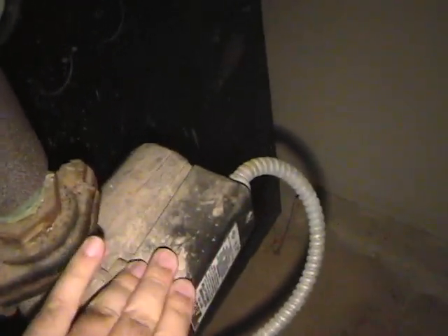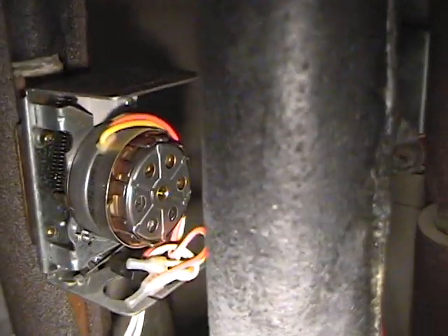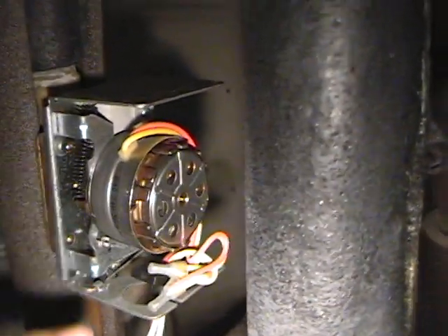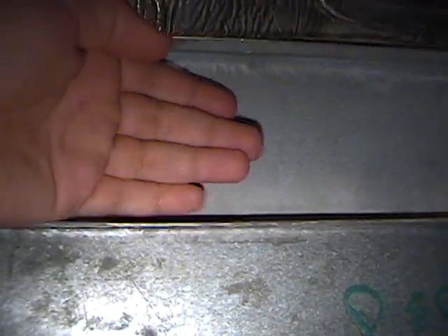Okay, so right now, move the tripod out of the way. Right now, as you can hear, the burner's heating up the water. As you probably heard, the pump's very quiet. It doesn't really make that much noise, and since this valve is open now, I'm not going to touch it because it's energized. Now the water's going up here into the heat exchanger for the first floor, and then once it gets hot enough, I'm gonna just tap this pipe. Oh yeah, that's hot. Once it gets hot enough, the thermostat will kick on and allow the fan to turn on. Oh yeah, this is hot right here, so it's doing well.